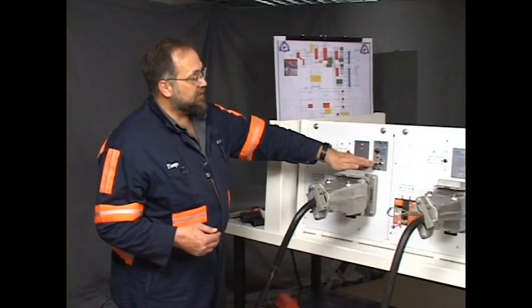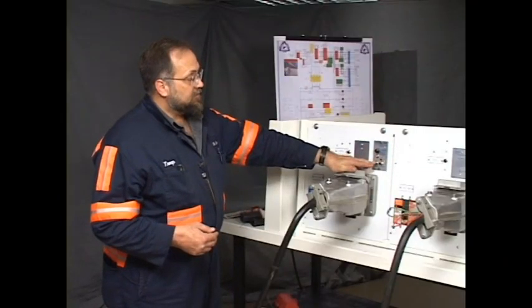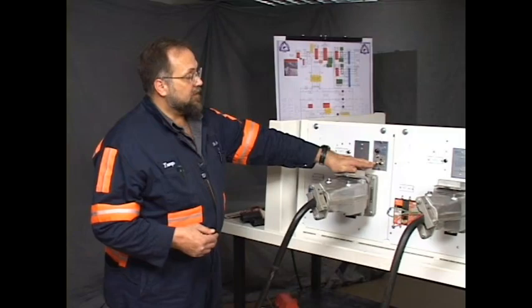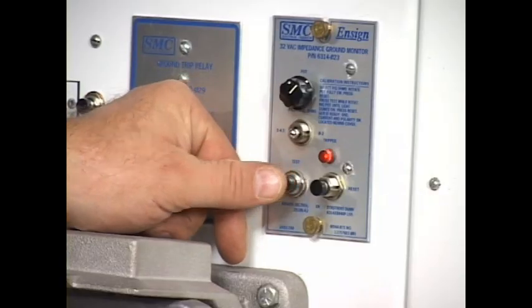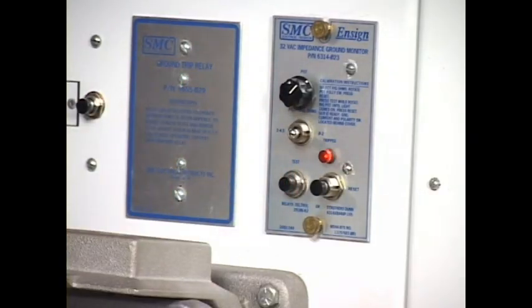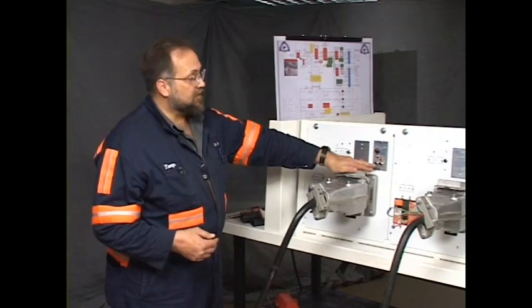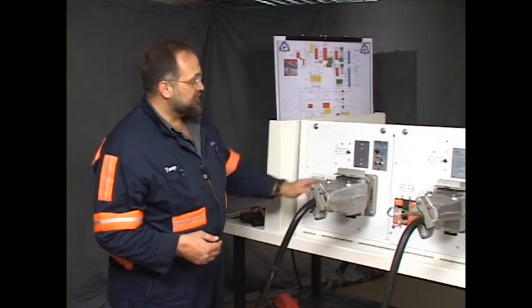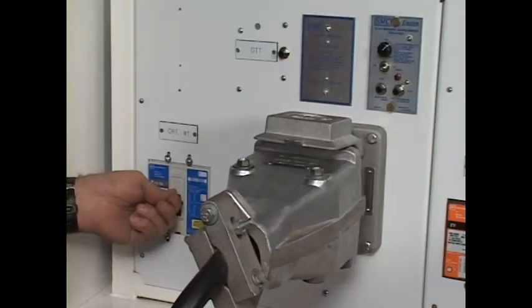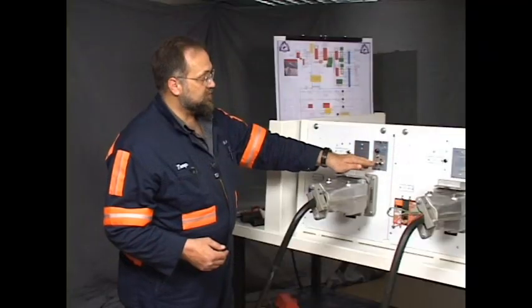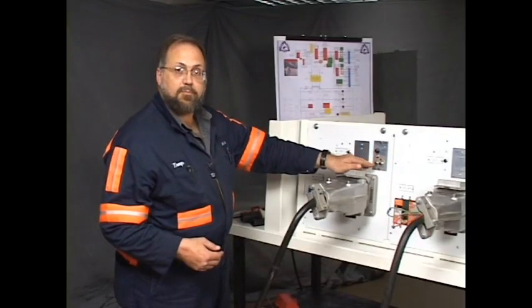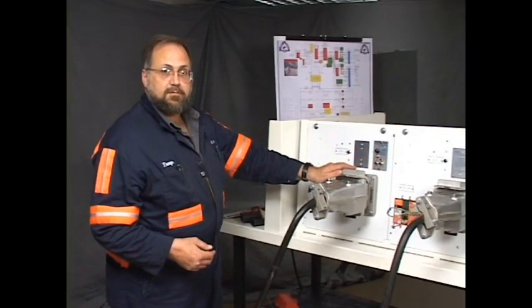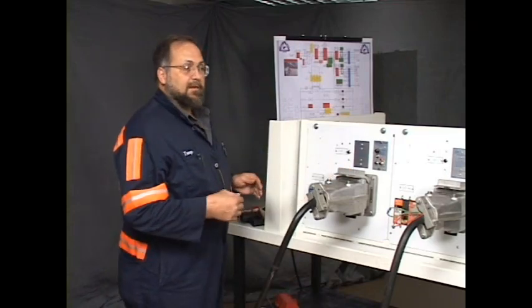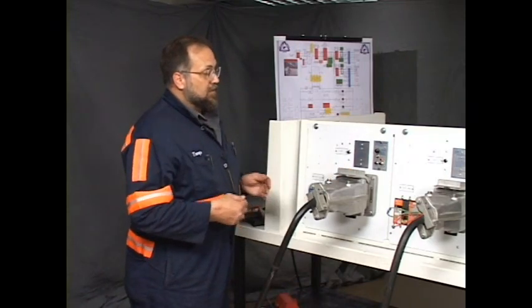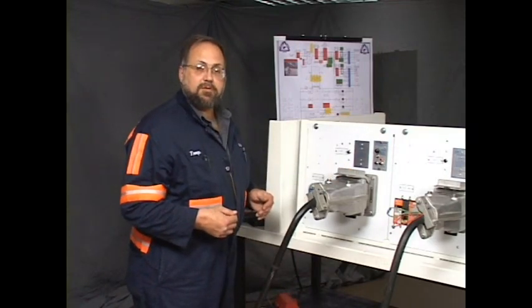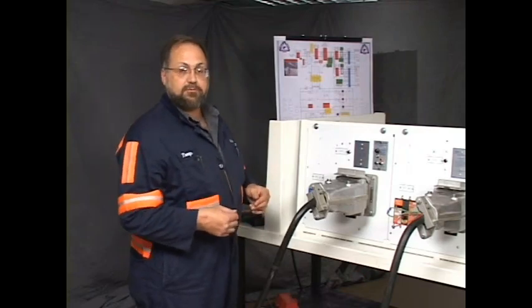This test button here is to check that. If the monitor is properly calibrated, when you depress the test switch, it trips and you have a red light. You can reset it. If the breaker is set, you depress the test switch, the breaker falls. And it's important to keep this thing calibrated as closely as possible, so that as you lose your grounding circuit, you're aware of it.